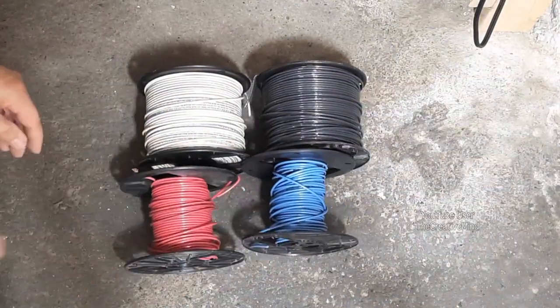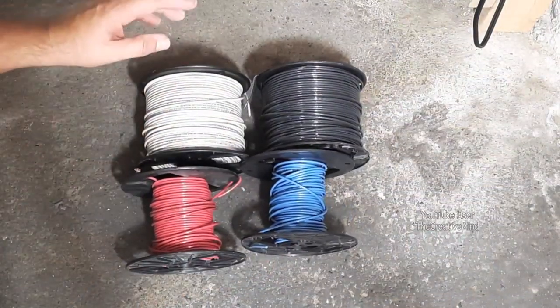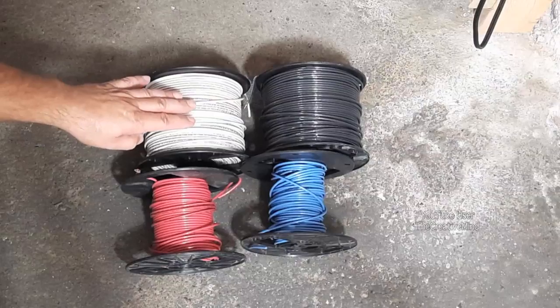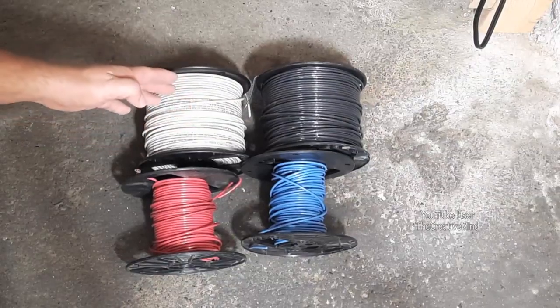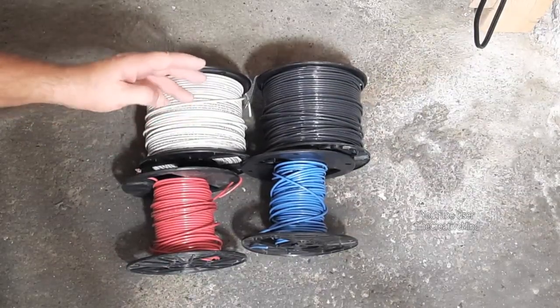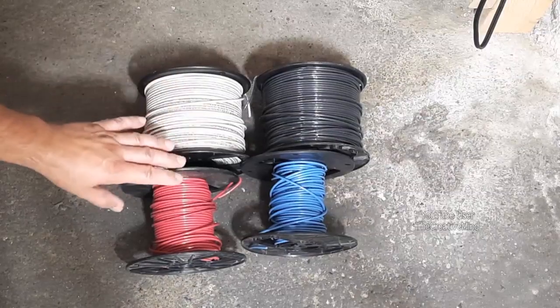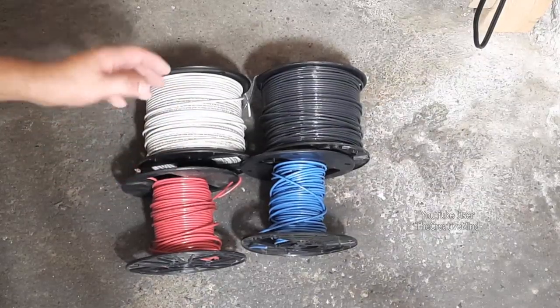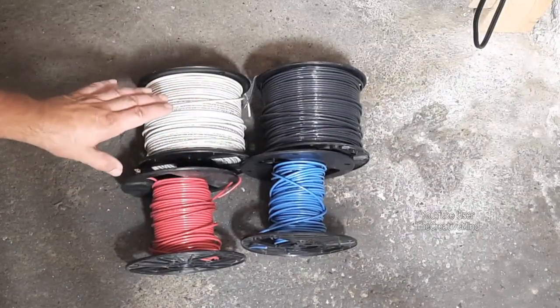The bus wire I'll be using in my demonstration is this number 12 stranded THHN wire. It's 600 volt rated on 500-foot reels, 20 amp circuit, 16 amps sustained copper wire, and this is the wire I use in my commercial and industrial projects.